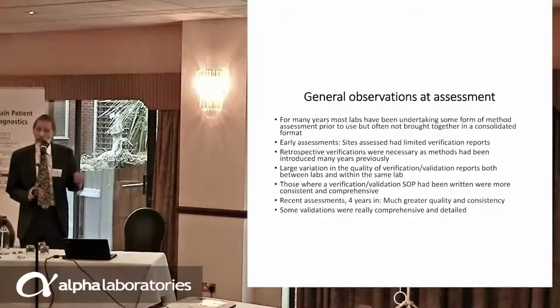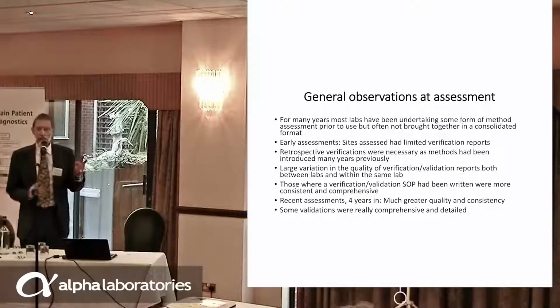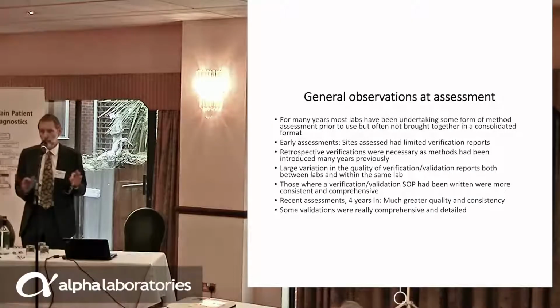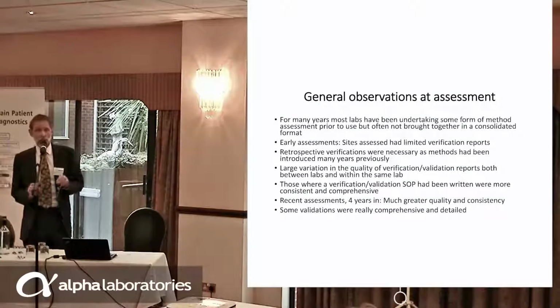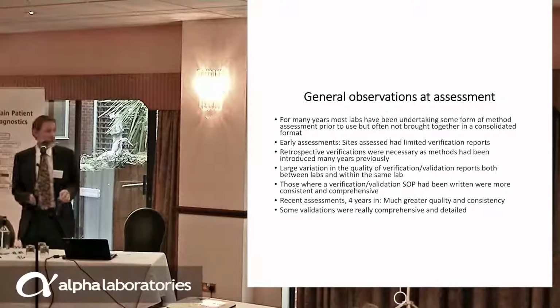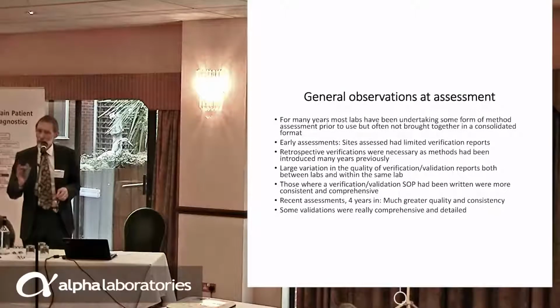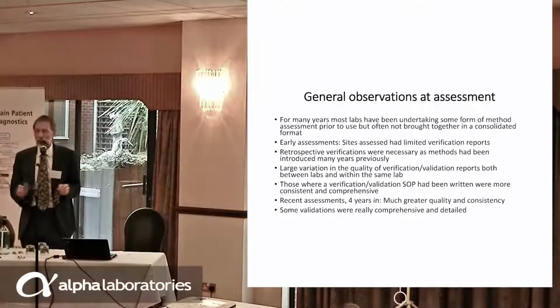My observation on the early assessments to ISO 15189 is that the verification reports were quite limited. So you'd go into a lab and say, okay, I see you've got a new analyzer, it was delivered 12 months ago, did you do a verification, can you show me some data? One of the things assessors are likely to do is to say, show me, okay? Because we want to see evidence, because what we're looking for is evidence of compliance with the standard. So, show me the evidence that you've done a verification.